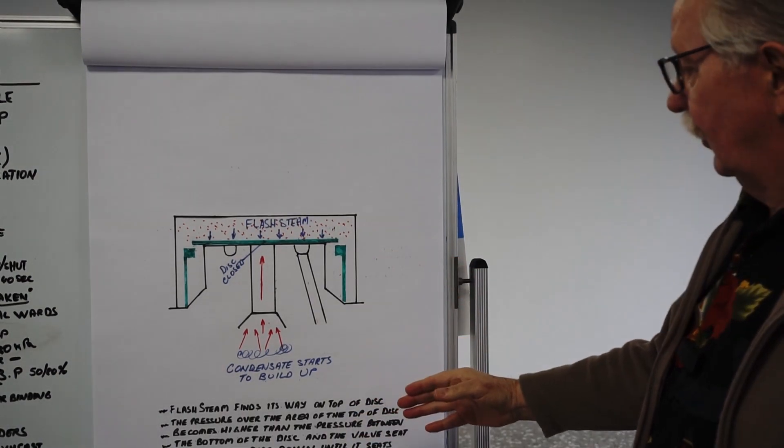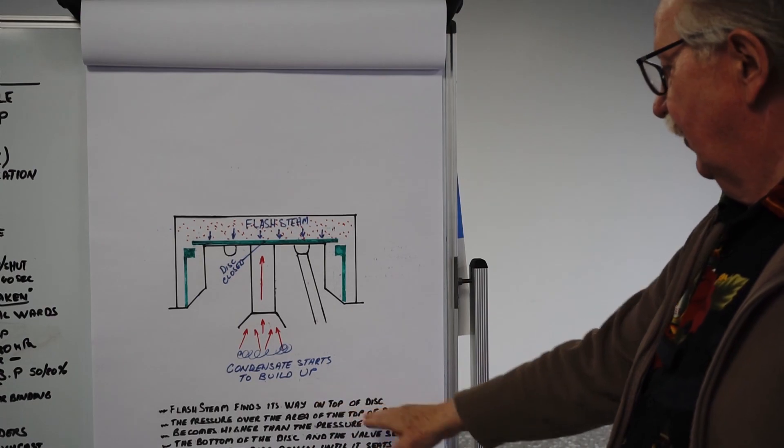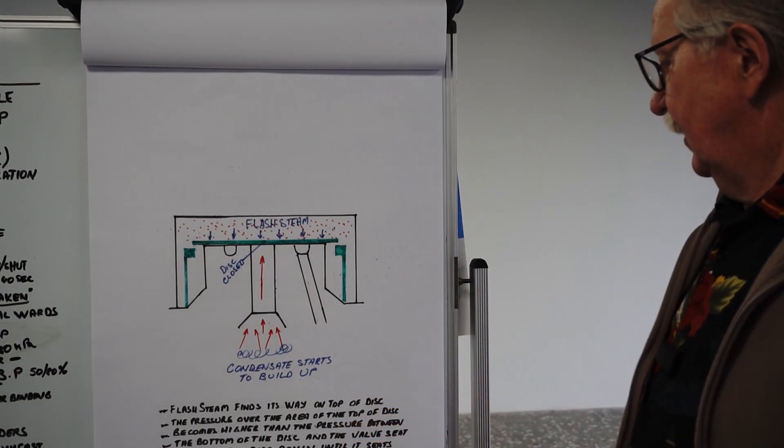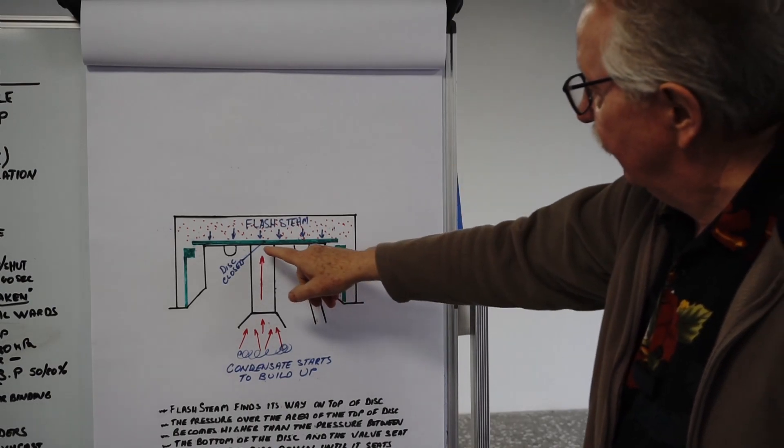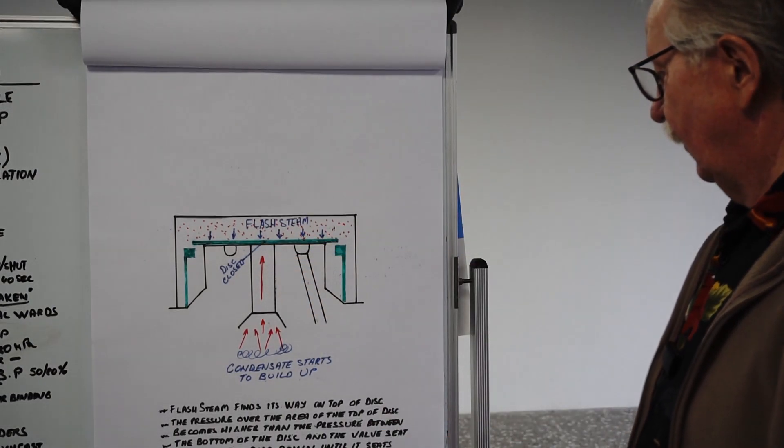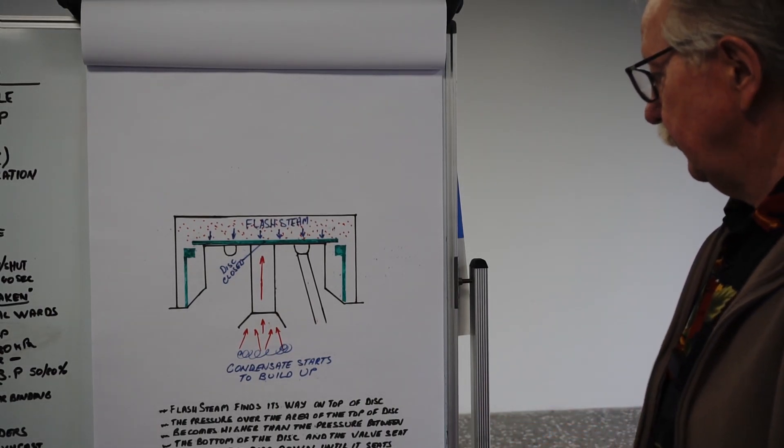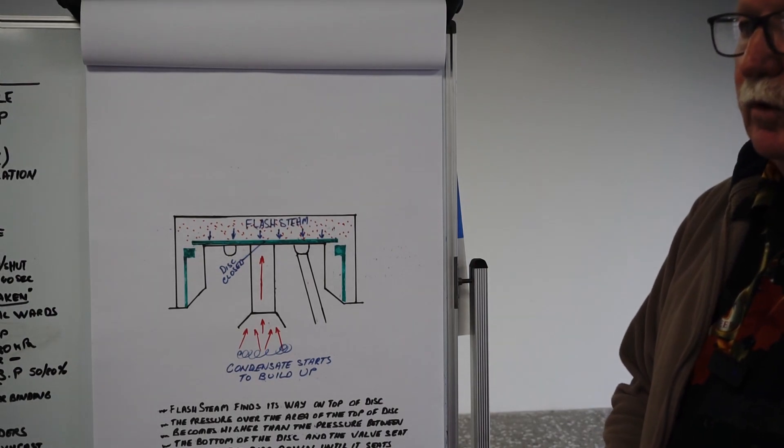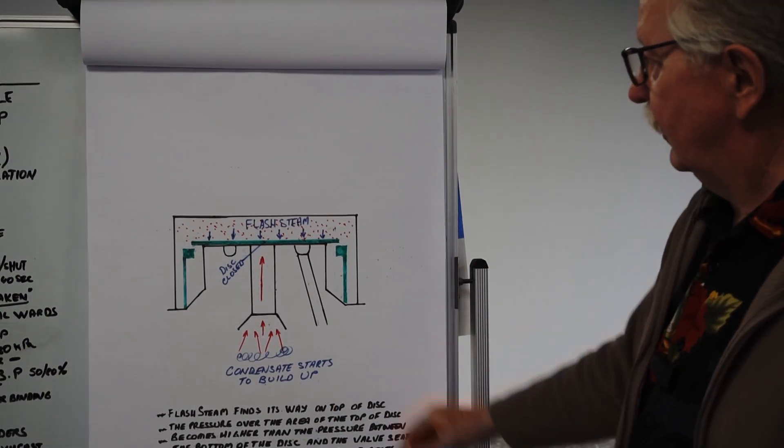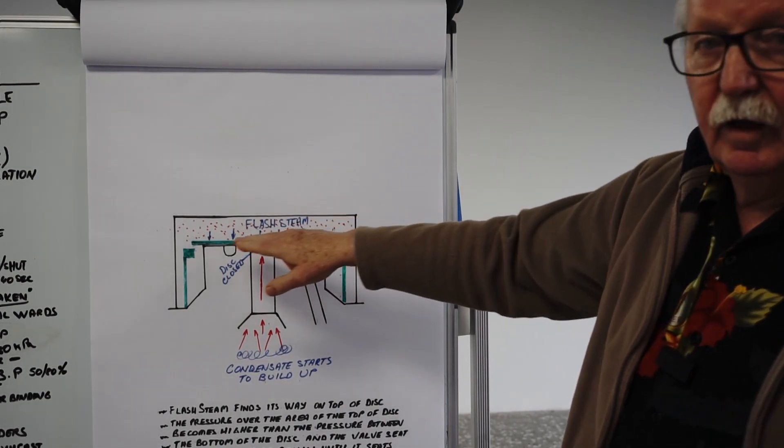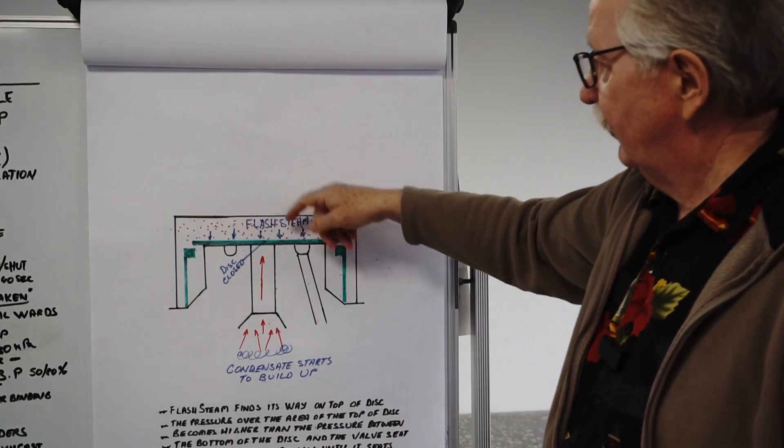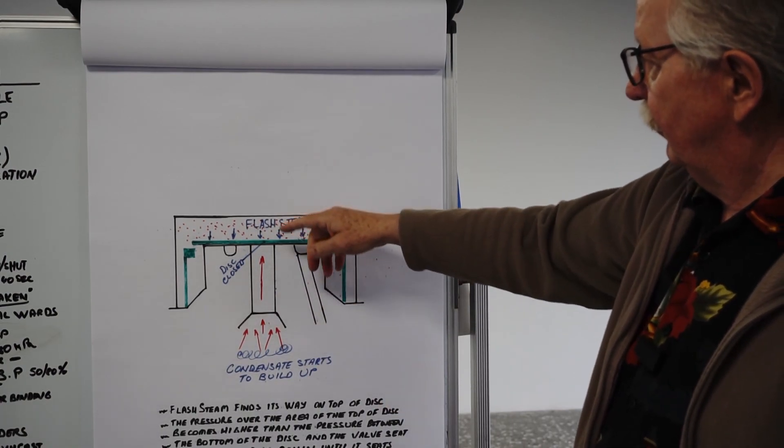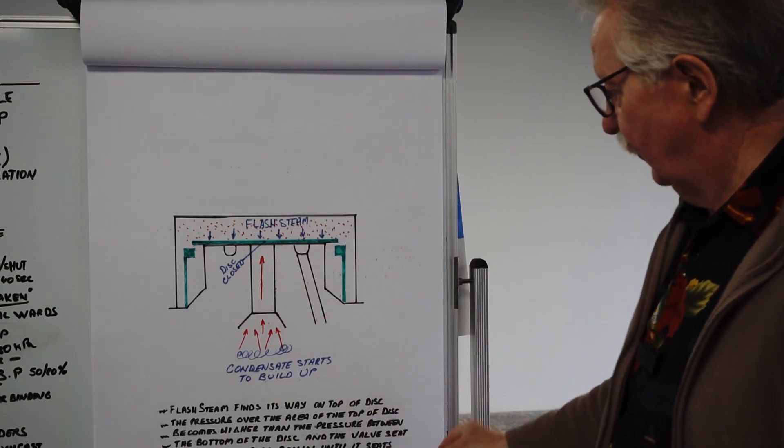I've sort of covered a lot of this in the other slide there, but what's happened here is the flash then finds its way up on top of the disc, forcing down on the larger surface area there. The pressure over the area of the top of the disc is greater than the small inlet port there, so it tends to overcome that and snap shut. Once it's forced down like that, condensate stops moving through the system and will start to cool down and build up in this area here. The cycle won't start until the flash steam that's in this control chamber radiates off to atmosphere and/or cools down sufficiently enough for it to condense. Once the pressure on the underside is greater than the pressure on the top, the cycle will start again.